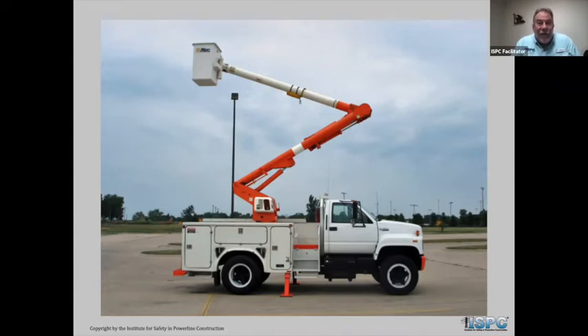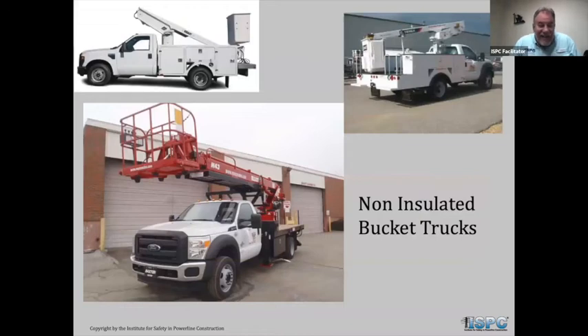You see the white part in the middle of that lower boom. That's a secondary insulation for that truck. Non-insulated bucket trucks, which most of our communication workers use, even though it looks like it may be fiberglass, if it is not tested on a regular basis, electrically, dielectrically tested, then it is considered a non-insulated bucket truck, even though it may be a fiberglass boom.